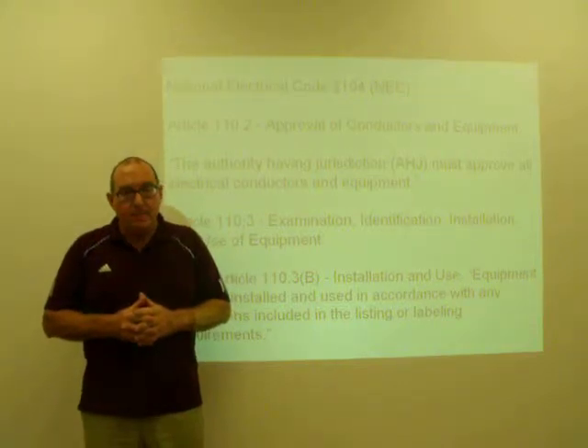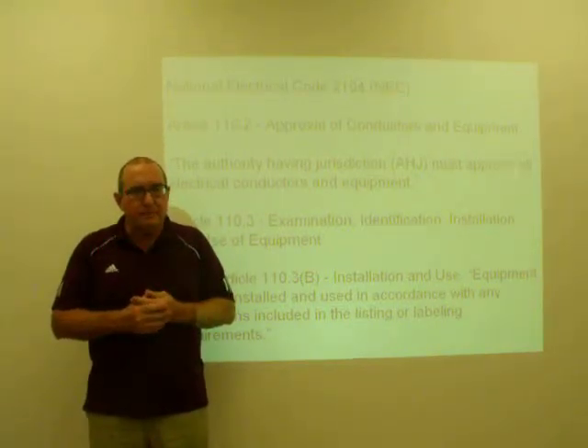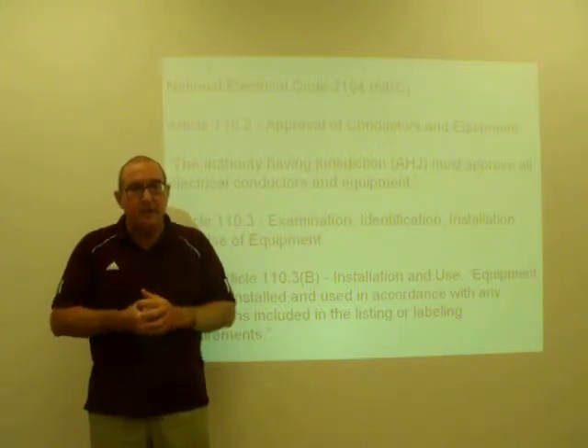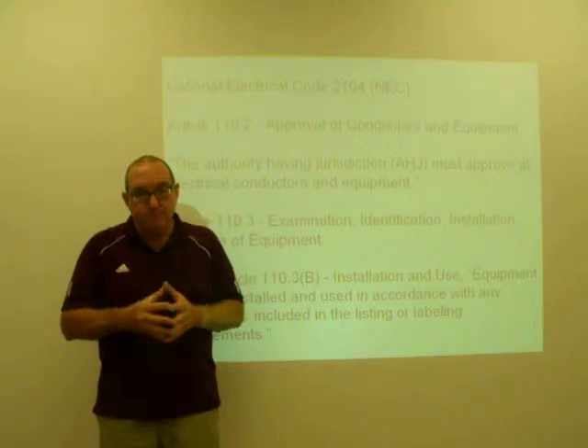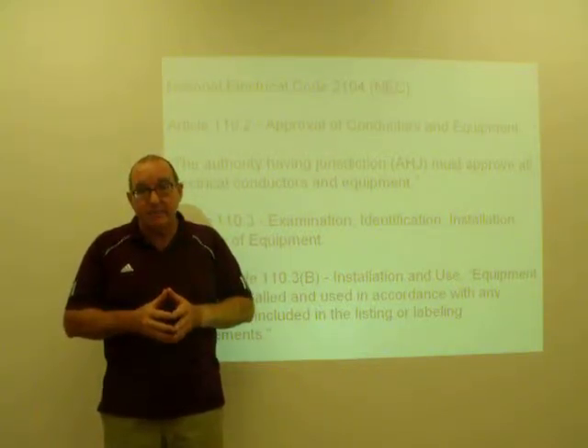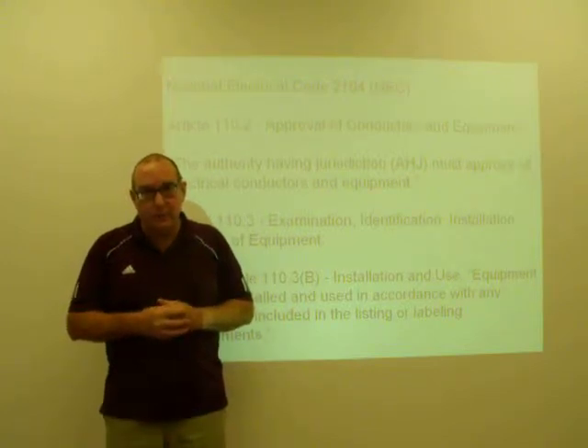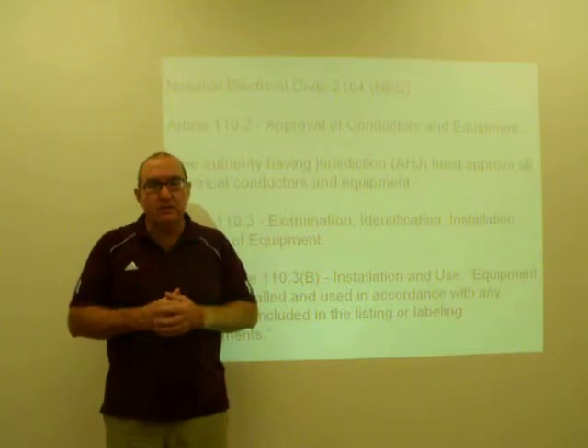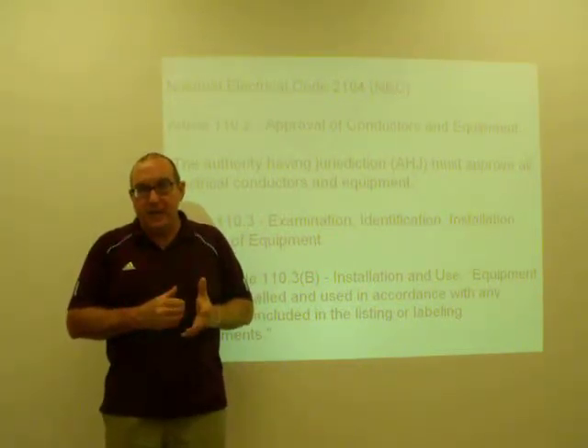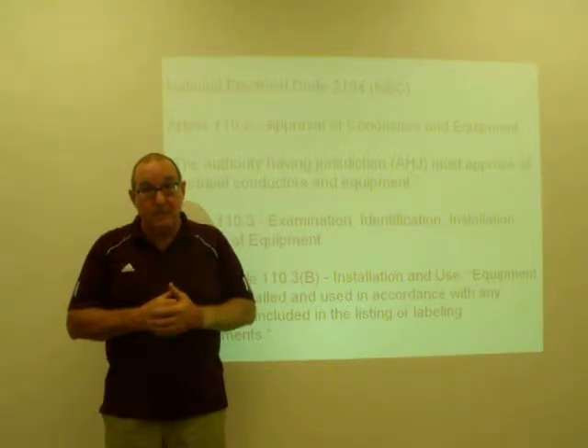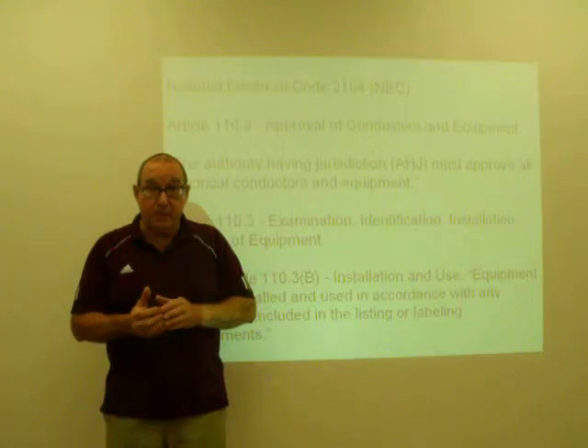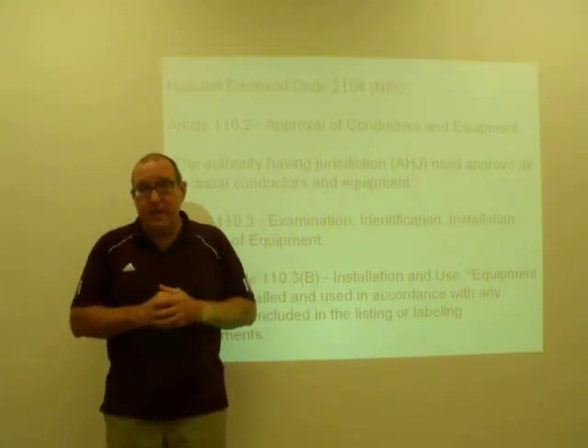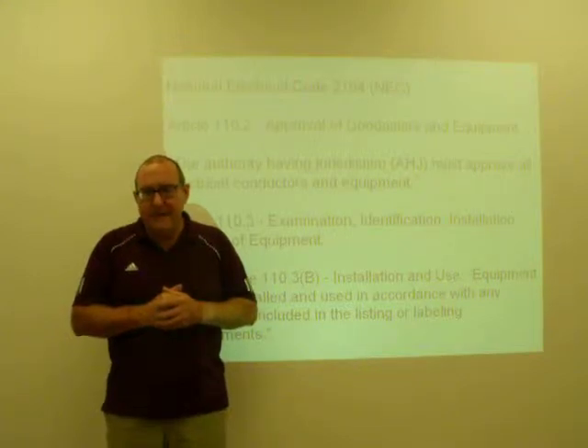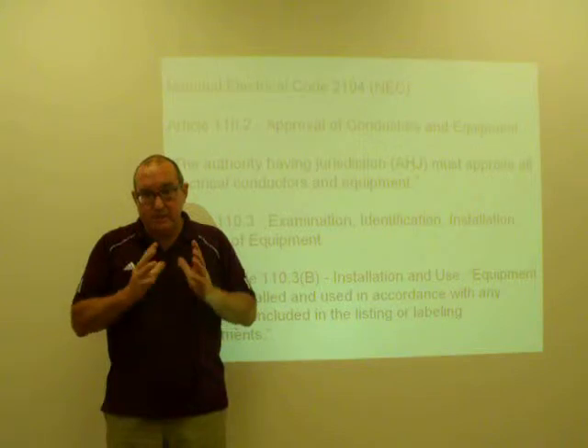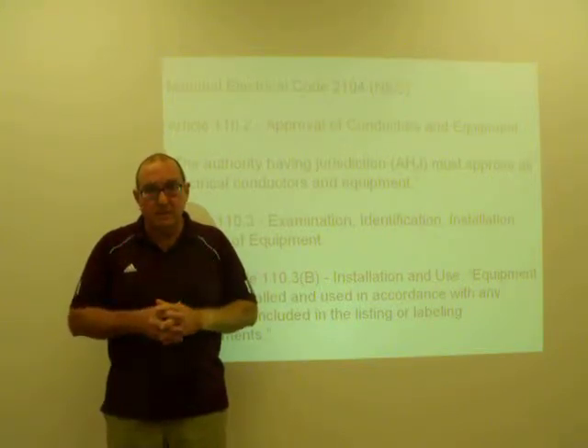The National Electrical Code, edition of 2014, abbreviated as the NEC. The two overriding articles here have to do with what you can do and what you cannot do in a general sense. The first is Article 110.2, approvals. The authority having jurisdiction, or the AHJ, typically your code inspector in the jurisdiction in which you are licensed to work, must approve all conductors and equipment. Now that individual, the AHJ, can make variances to the code, can disapprove something the code says should otherwise be authorized, can approve an application that the code might otherwise not really authorize, but if the inspector insists that it's perfectly legal, then you're allowed to do it.